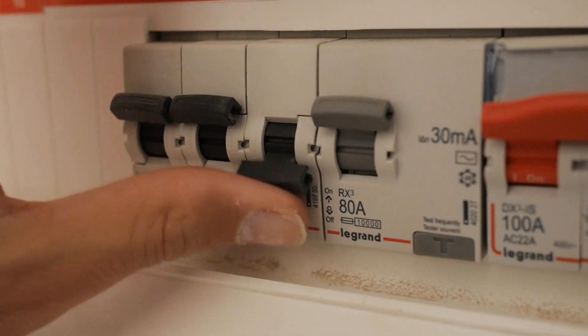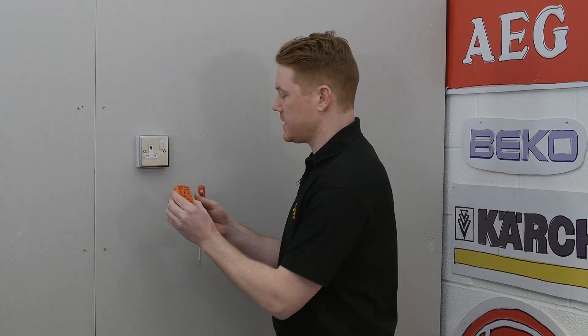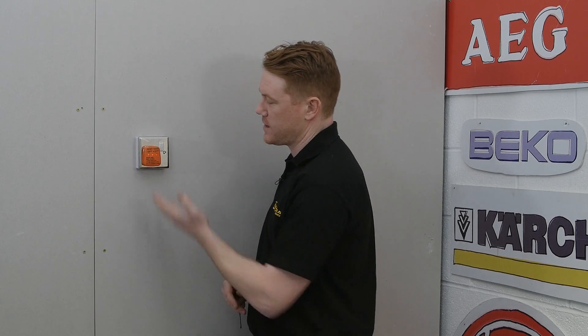Once you're happy that the socket is firmly in place, reset the relevant fuse at your fuse board. You can then grab your handy plug-in socket tester, and there we have it - all three lights, meaning that the socket is wired correctly.